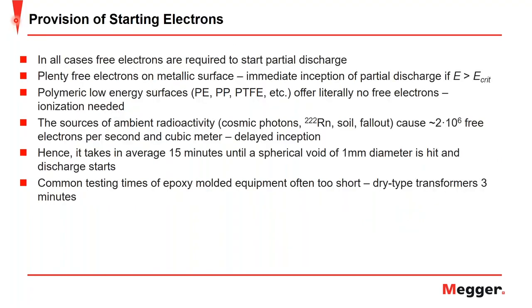So when we talk about starting electrons, there's provisions for starting electrons that change depending on the material. But one thing is certain. In all cases, free electrons are required to start partial discharge. So if there are no electrons, there is no partial discharge activity.